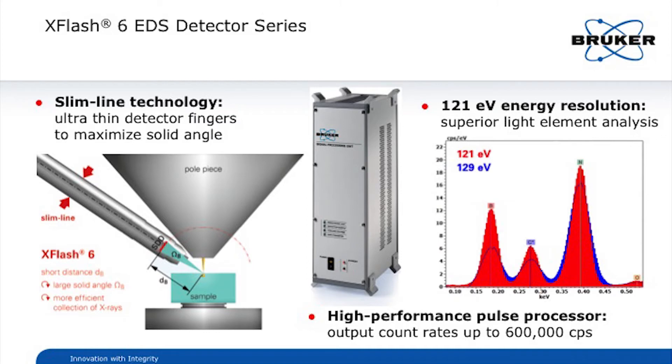A high performance pulse processor with an output count rate of up to 600,000 counts per second coupled with an energy resolution down to 121 eV provides the highest quality spectra for precise analysis, especially in the light element and low energy range.